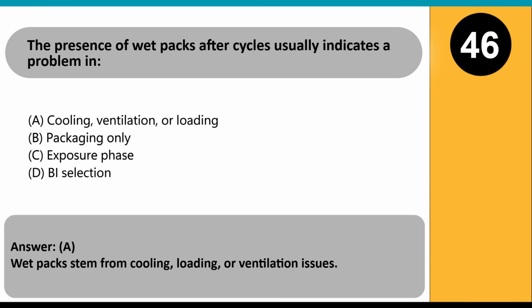The presence of wet packs after cycles usually indicates a problem in A. Cooling, ventilation, or loading. B. Packaging only. C. Exposure phase. D. BI selection. Answer: A. Wet packs stem from cooling, loading, or ventilation issues.